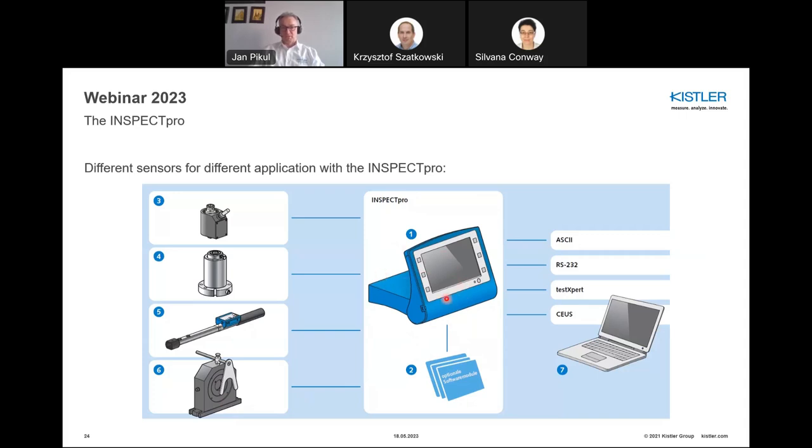If you want to, for example, test tools, we can use the stationary transducer, which can measure only torque. For other applications like in-process measuring, we use a rotary transducer, which can also be connected to one channel. All this data can be transferred to the PC as a text file and can be analyzed by the user on its own software.